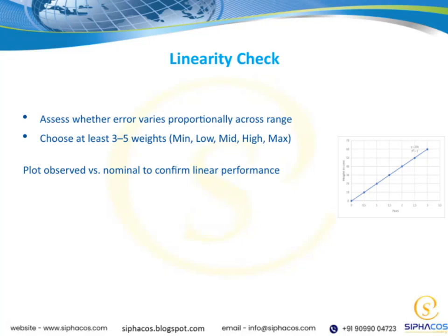Let's move on to the linearity check. Here, we're assessing whether the error varies proportionally across the entire range. To do this effectively, we should select at least 3 to 5 different weights, covering the minimum, low, mid, high, and maximum points. By doing this, we can see how the system responds at various levels.